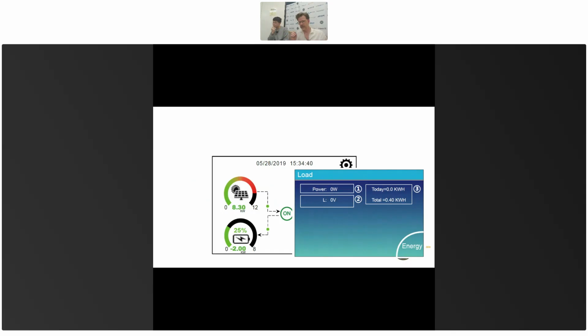So often people will say, oh, I've set up the system and the loads are not on, and it might just be waiting. If you click down onto the load terminal, you'll see the load voltage, and that will build up until it gets to 230, and then it will engage. So if the load terminal isn't turning on and you see it slowly rising, chances are it's going to turn on in a minute or so. But if the voltage is just 0 and not moving, then you've got a problem somewhere else.